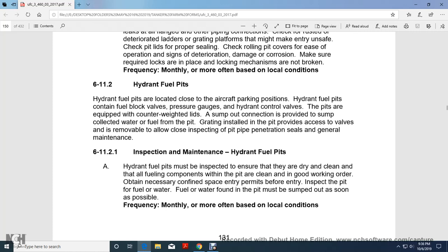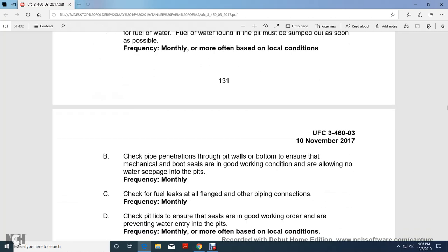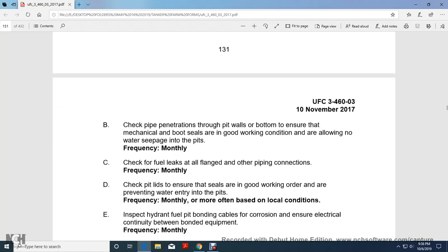Obtain the necessary confined space entry permits before inspecting the pit for fuel or water. Fuel or water found in the pit must be sumped out as soon as possible, monthly, or as often as needed based on local conditions. Check pipe penetrations in the pit walls and bottom to ensure the mechanical boot seal is in good working condition, allowing no water seepage into the pits, monthly.